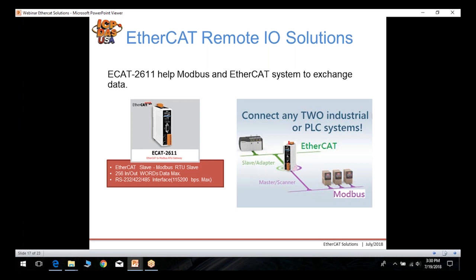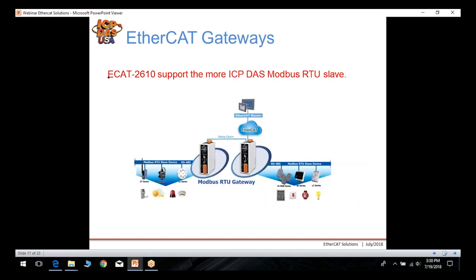The EtherCAT slave module has up to 256 input and output words maximum and is communicable by RS-232, RS-422, and RS-485 for the Modbus side. The ECAT 2610 topology allows you to daisy chain Modbus gateways.